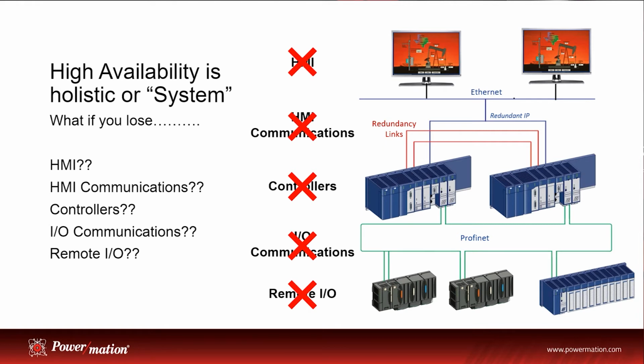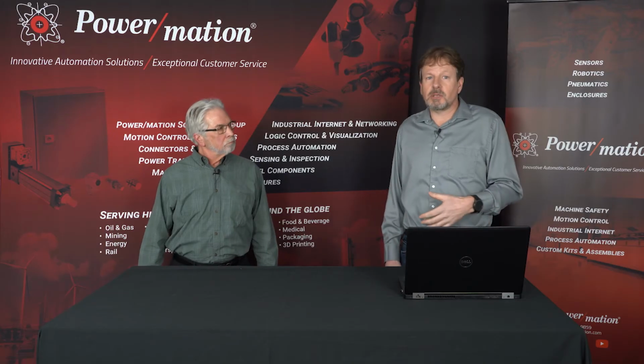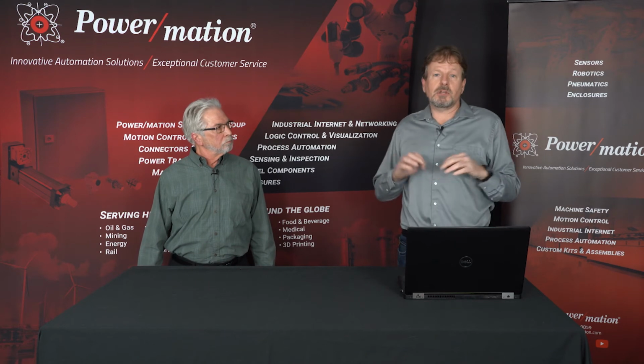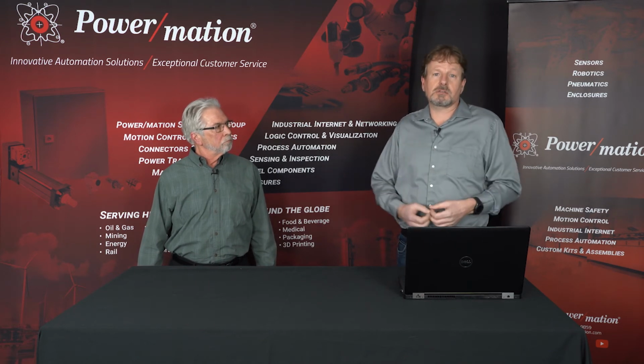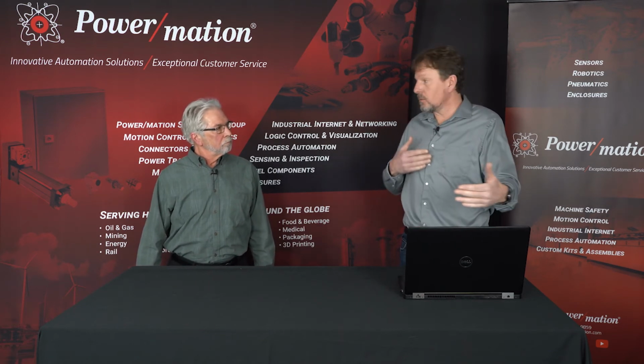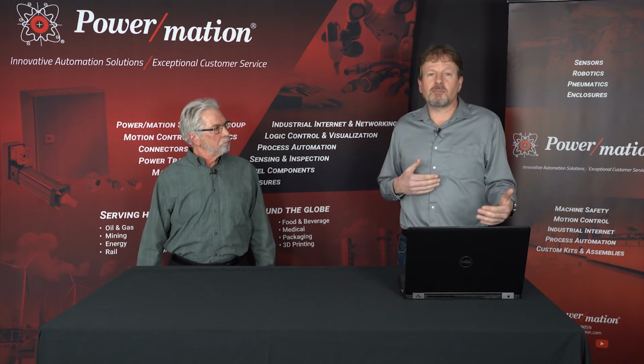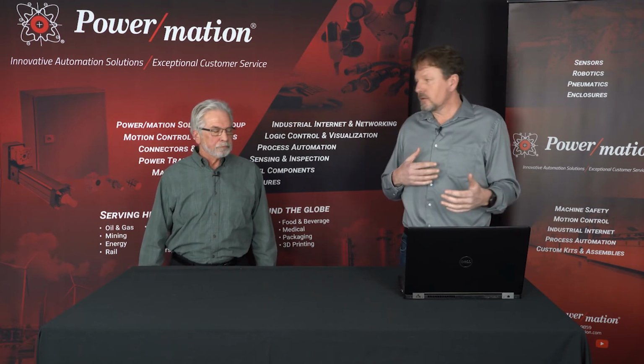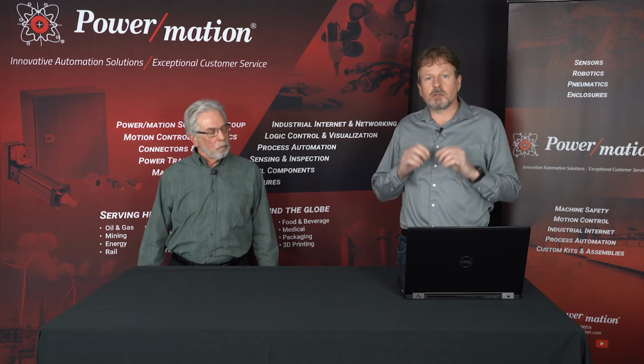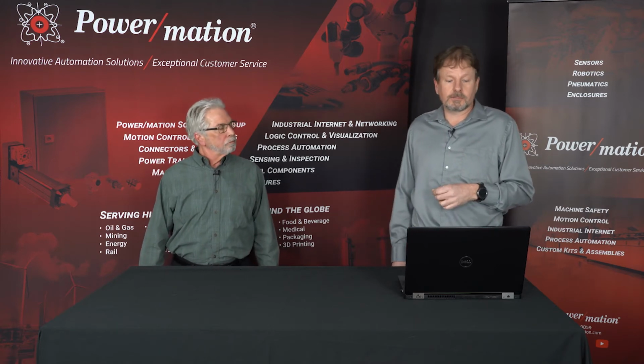And then you get down into the control level and say, well, what if we had a single controller, just one box controlling the whole process, but we're very vulnerable to outside, maybe lightning events, maybe people digging underground or something like that. Maybe it goes across parking lots. Maybe we need two methods of getting communications out to our I/O. Maybe this tunnel that we're talking about is 3 or 4 or 5 miles long. And so maybe we want different paths of communication. So that's where you get redundant on the I/O communications.